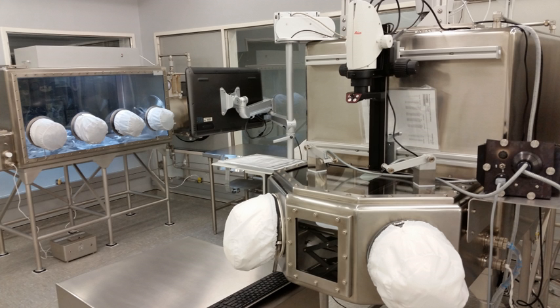The facility takes extensive measures to prevent contamination of the lunar samples. All materials used in constructing and equipping the building — including floor coverings, walls, plumbing, light fixtures, and paint — were carefully screened to exclude chemical elements that would pose unacceptable contamination threats to the lunar samples. Air in the facility is filtered to remove all suspended particles, and the air in the laboratories and vaults is maintained at slightly higher than atmospheric pressure to keep unfiltered air from entering. The particulate concentration of the air in the various areas is monitored regularly, and people entering laboratories and vaults are required to don cleanroom suits.